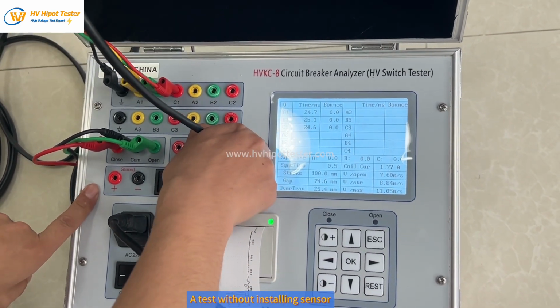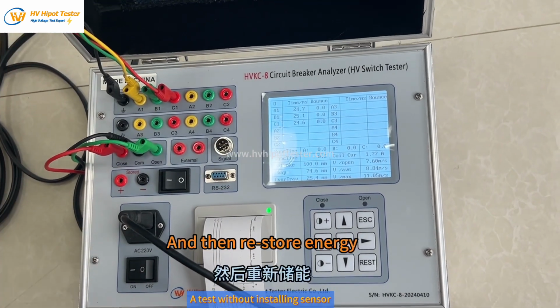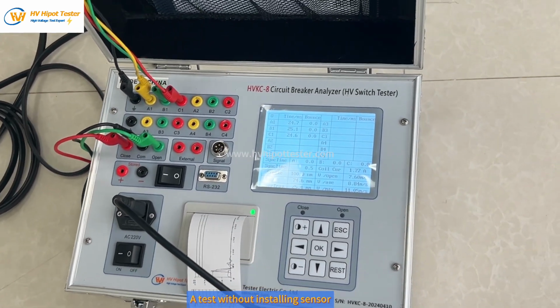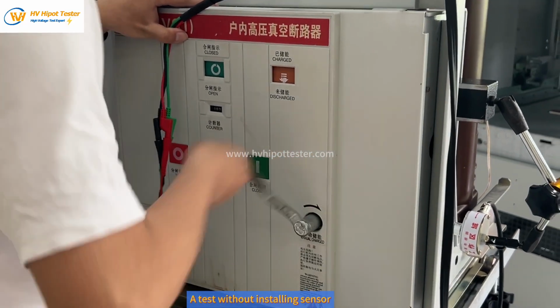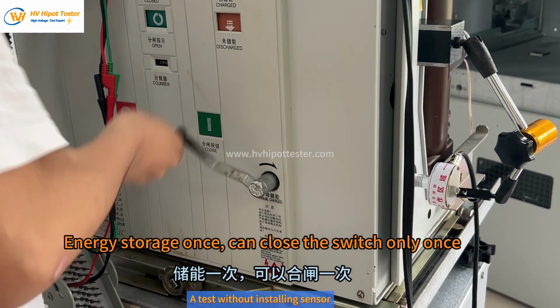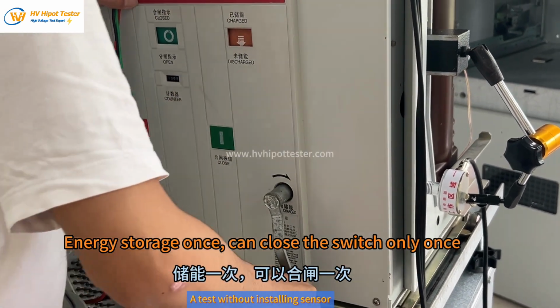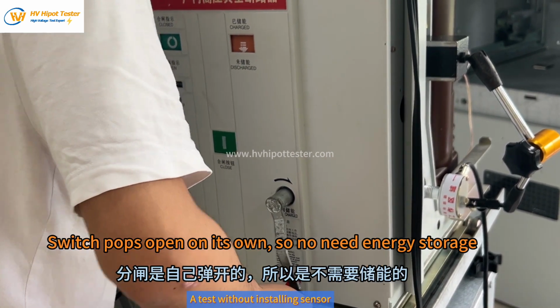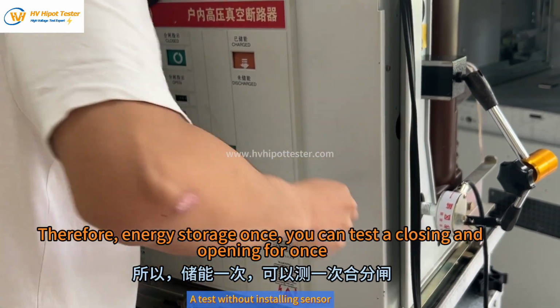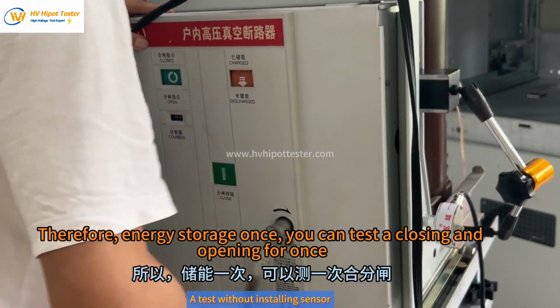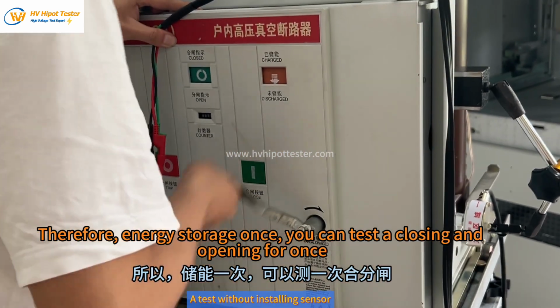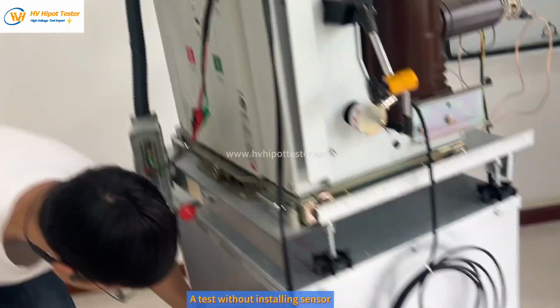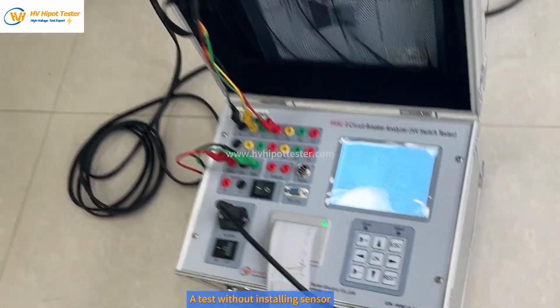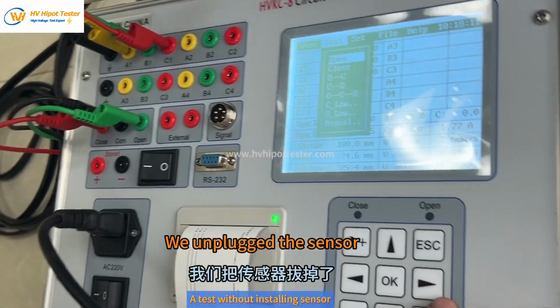Do a test. We unplug the sensor and then restore energy. Energy storage once can close the switch only once. Switch pops open on its own, so no need energy storage. Therefore, energy storage once, you can test closing and opening for once. We unplugged the sensor.